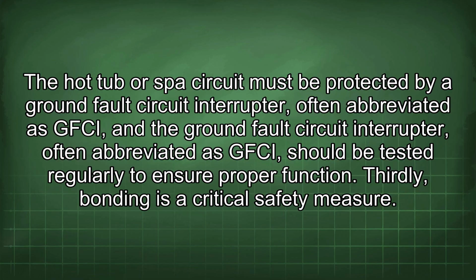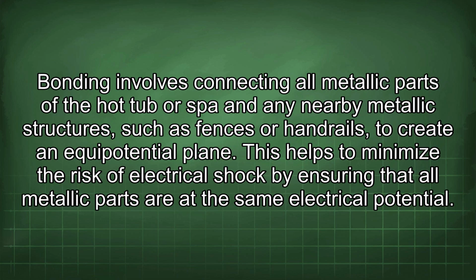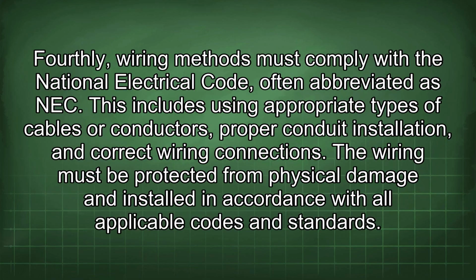Thirdly, bonding is a critical safety measure. Bonding involves connecting all metallic parts of the hot tub or spa and any nearby metallic structures such as fences or handrails to create an equipotential plane. This helps to minimize the risk of electrical shock by ensuring that all metallic parts are at the same electrical potential. Fourthly, wiring methods must comply with the National Electrical Code. This includes using appropriate types of cables or conductors, proper conduit installation, and correct wiring connections. The wiring must be protected from physical damage and installed in accordance with all applicable codes and standards.